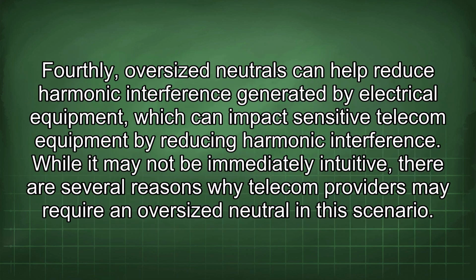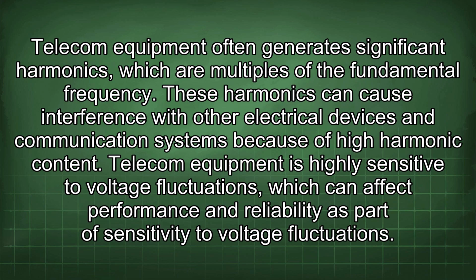Fourthly, oversized neutrals can help reduce harmonic interference generated by electrical equipment, which can impact sensitive telecom equipment. While it may not be immediately intuitive, there are several reasons why telecom providers may require an oversized neutral in this scenario. Telecom equipment often generates significant harmonics, which are multiples of the fundamental frequency.